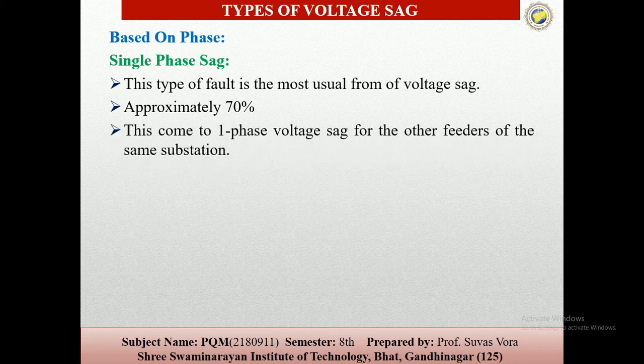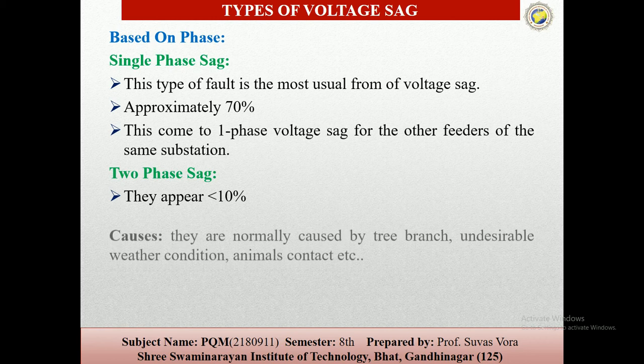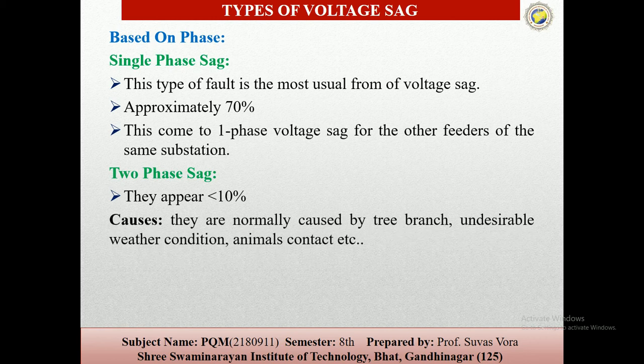So these come as single phase voltage sag from other feeders of the same system or substation. Then the two phase system appears in less than 10% of cases. Two phase faults are line to line fault, then line to ground fault. They are normally caused by tree branches, undesirable weather conditions, animal contacts and so on.